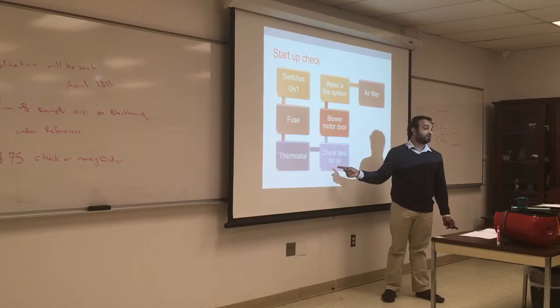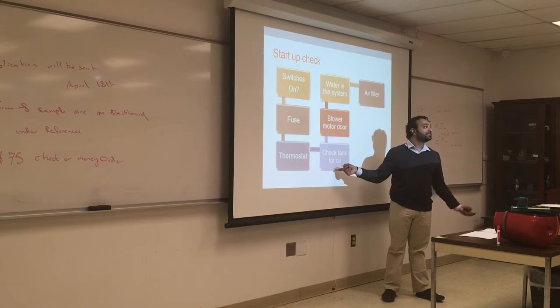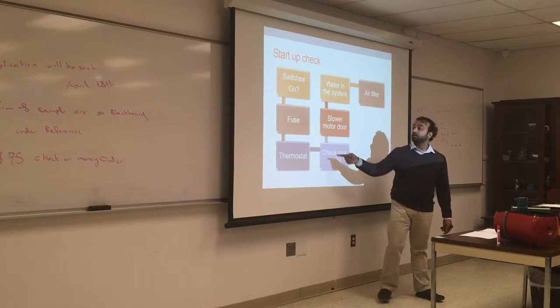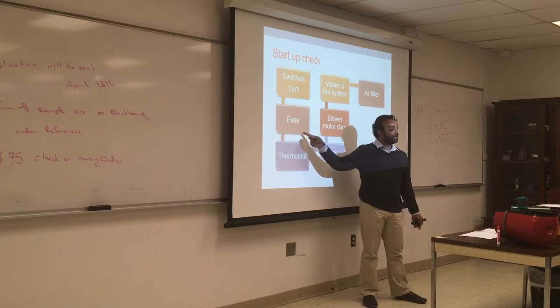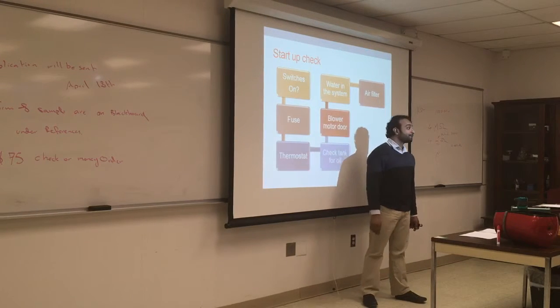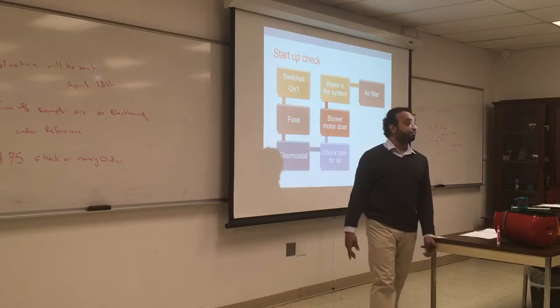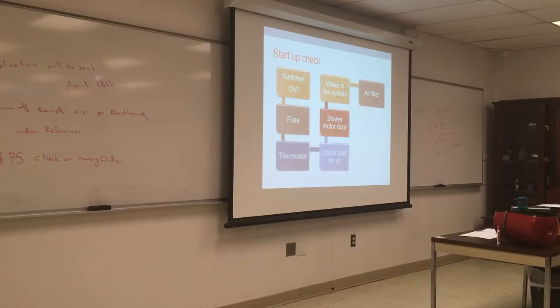Here is a simple mistake that everybody makes: never look at whether there is oil in the tank. Seriously, there is no oil in the tank. The whole thing, there is a startup and checkup, electricity, is there oil? It's very simple, but it happens a lot. The fuse is a lot of times an issue. And the switch, I can tell you at least 3 or 4 times, the emergency switch by the stairs when you go down the basement, there's always a red switch. Somebody turned it off, and the system is not working, thinking it's the lights. So that could be an issue.